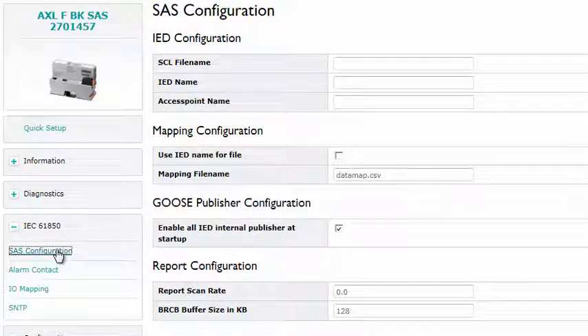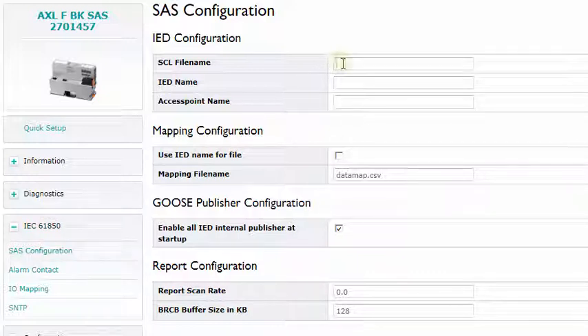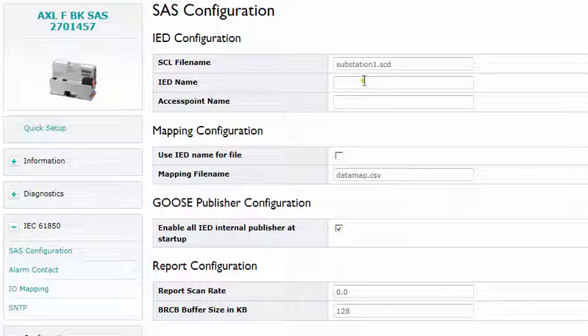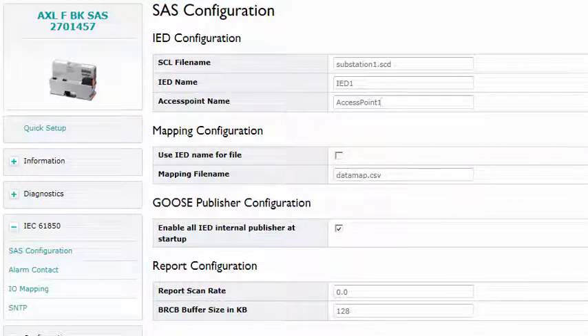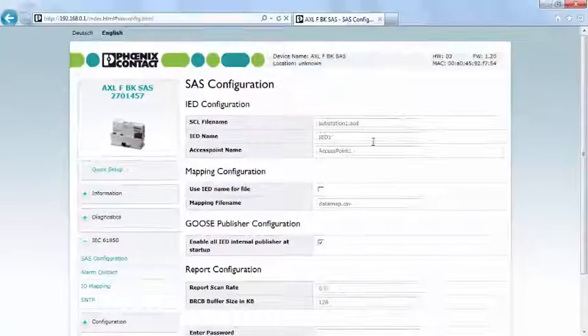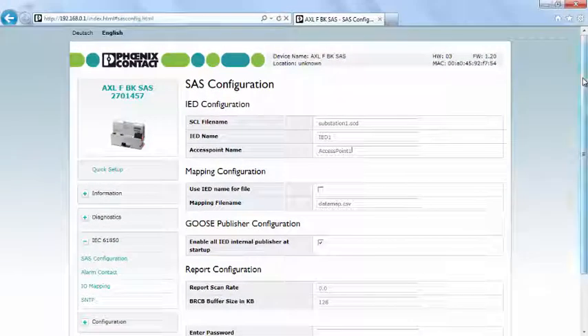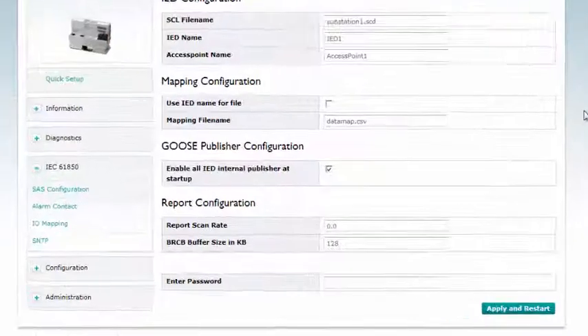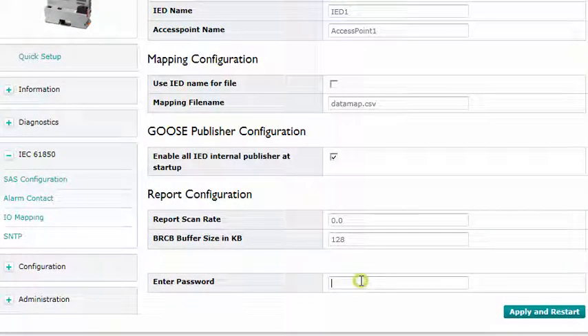Open the item SAS configuration under the category IEC 61850 and make the following entries: the file name of the configuration file is substation1.scd, the name of the IED is IED1, and the access point is called access point 1. Note that the entries for the names are case sensitive. The settings are applied after entering the password and restarting.